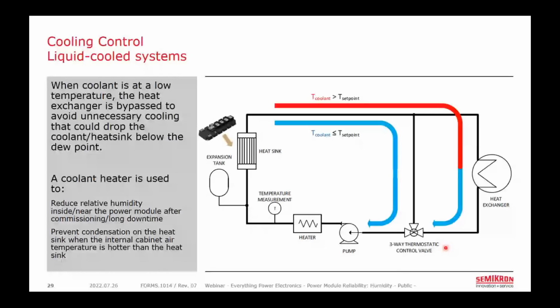In very large systems, there is even something called a coolant heater, which is very useful for making sure that the heatsink temperature is never below the ambient air temperature, thereby avoiding reaching that dew point. And additionally, it lets us warm up this heatsink before starting a system, which, as we know, will reduce the relative humidity as shown in this next slide here.